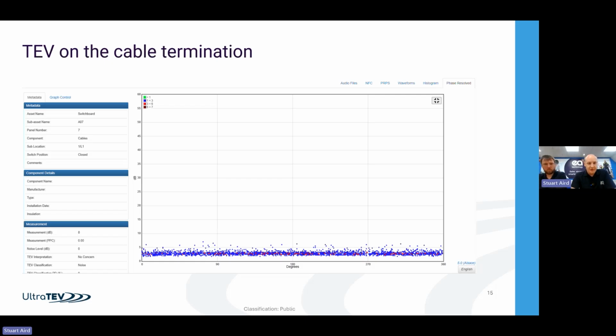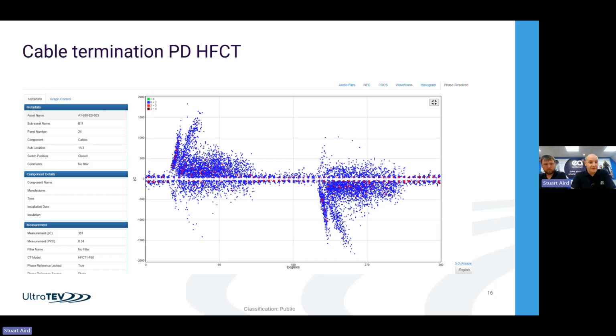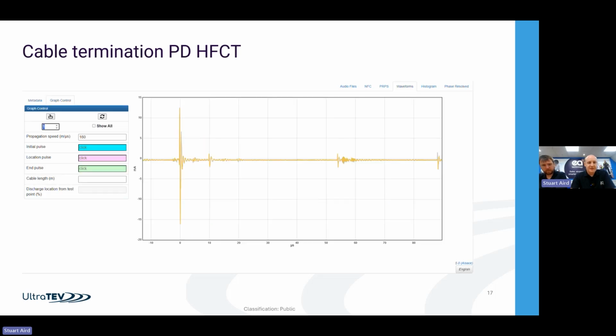But then we went to another circuit, again with an HFCT measurement. Again, you can see the initial pattern is slightly different, much stronger, and does have these leading edges in there. So it looks a bit more like a possible internal void type problem, and it's much stronger. So again, we carried out the analysis and we had a look at the waveforms. The difference in the waveform is this is much faster. So it's indicating that it could be very local to the cable termination.